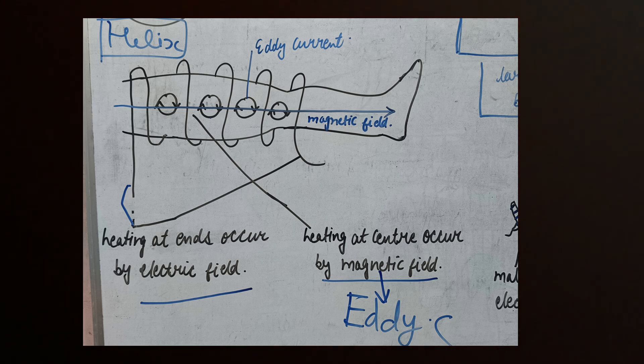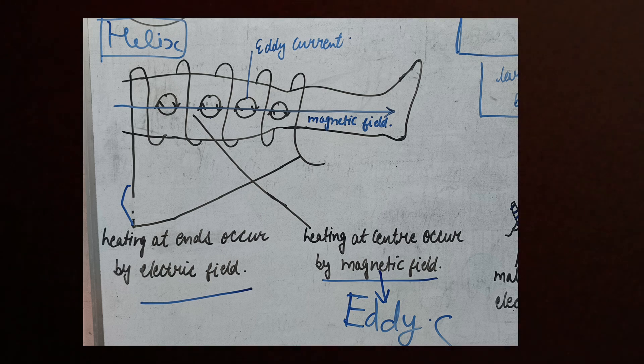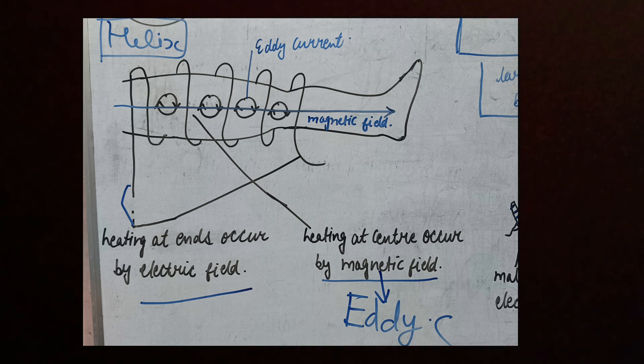Or we can use air spacing, but it is difficult to handle — you would just place the cable away from the skin, which is difficult to manage. So in most cases we use a towel to produce the spacing between the cable and the skin. The center has development of the magnetic field, while at the end the electric field is developed. This applies to both the helix and spiral arrangements.